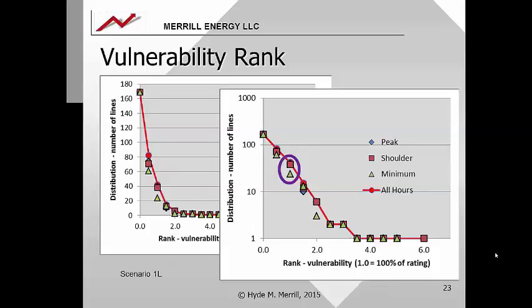I've got to be careful the way I say this - I didn't say it quite right. It doesn't mean there's one single line that will cause 40 other lines to overload. It means there are 40 lines that can overload, subject to overloading if some other line overloads. It could be a different line for each - 40 different lines, one for each of the overloaded lines. And here we have maybe a dozen lines that reach 150% or more of their rating with the outage of some other line.